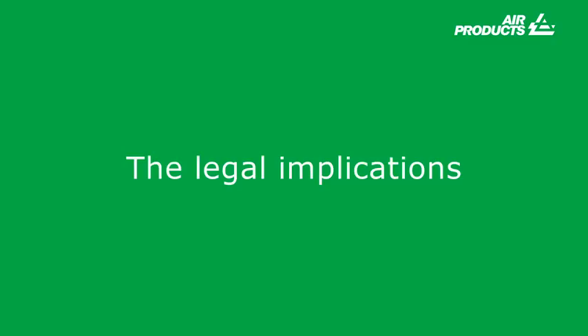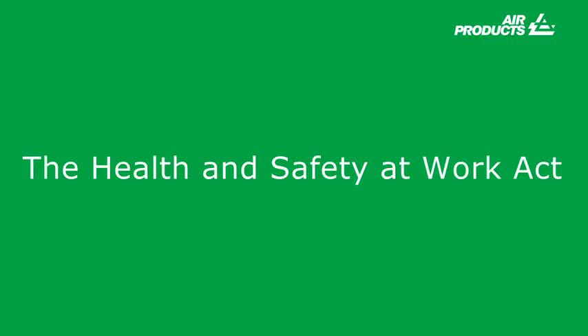The legal implications then? Well, as the end user, you can decide to follow or not the standard and guidance document. But if you don't follow the manufacturer's instructions and there was a subsequent incident, you would almost certainly have to explain why you didn't follow best practice by adhering to the manufacturer's guidance. The Health and Safety at Work Act tells us what we must do and how this would appear to reinforce bump testing as a legal requirement.